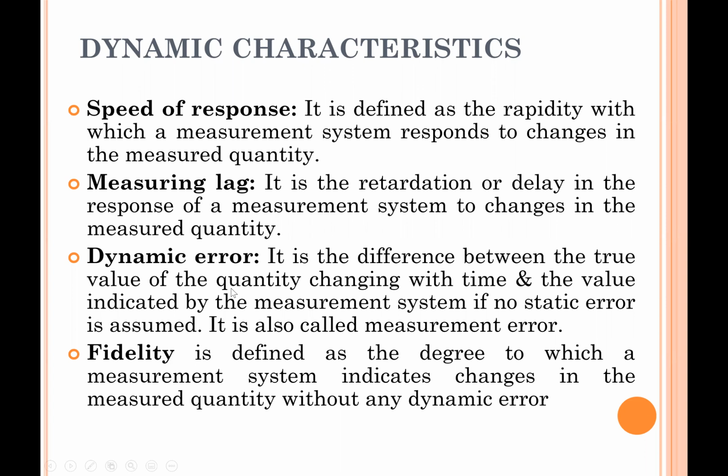Okay, now it is the retardation or the delay in the response of the measurement system towards the changes in the measured quantity. Measuring lag usually picture में कब आता है, जब हमारे पास कोई remote measurements हो रहे होते हैं. ठीक है, for example, if I am measuring something in the field but it is being displayed somewhere in the office at some physical distance, in that case जब तक हमारा signal travel करेगा for different stages, amplification के लिए या कोई भी modulation हमें उसमें करनी है, कोई manipulation करनी है, जब तक वो finally display पे आता है, जब तक वो finally हमें value मिलती है, तब तक there is slight delay because of that transmission that is taking place.